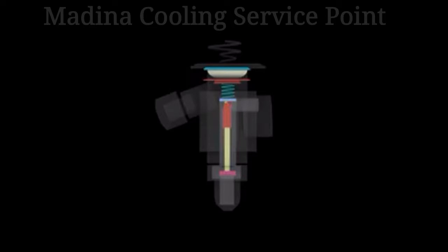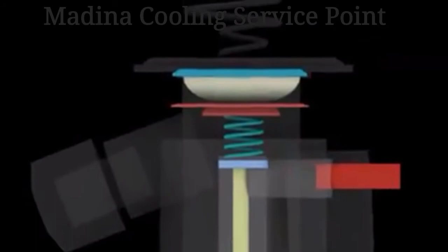After some time, when the temperature inside the refrigerator falls to the desired value, the mercury will contract. The pressure drop above the diaphragm causes the spring to lift up the push pin and close the valve. The refrigerant will stop flowing, and at some point after the valve closes, the compressor will cut off.